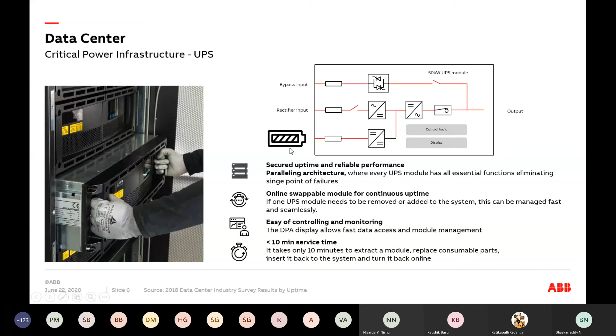Of course, there are different topologies available. We won't go through all the details, but typically there are modular designs, with either vertical and horizontal scalability of UPSs, or only horizontal scalability. In vertical, you have modules embedded into the UPS, starting maybe from 10 kVA, 20 kVA, up to 200 kVA per modular device, with total power going up to 3.8 or 4 megawatts for all the UPS. In horizontal scalability, they start from around 120 kilowatt and go up to 3.8 or 4 megawatts. Typically, data center power ranges start at the megawatt range but can go up to 500 megawatts total power consumption within the devices.